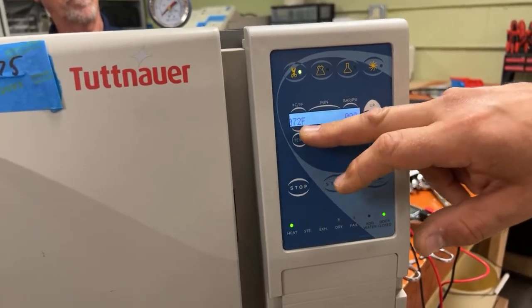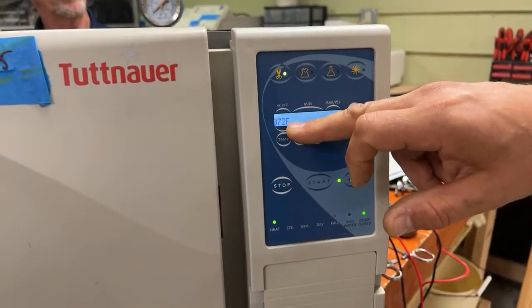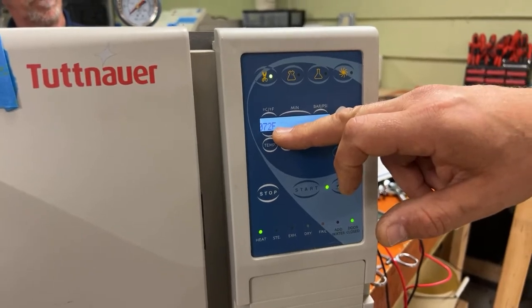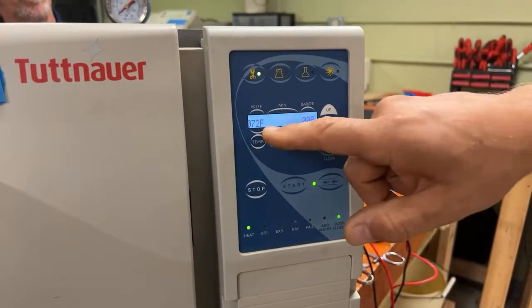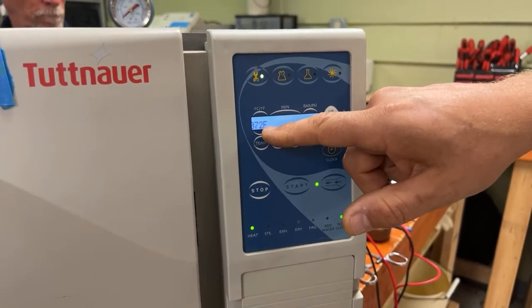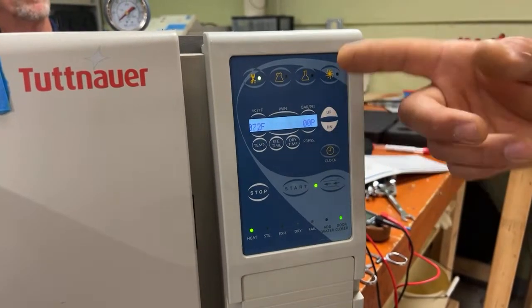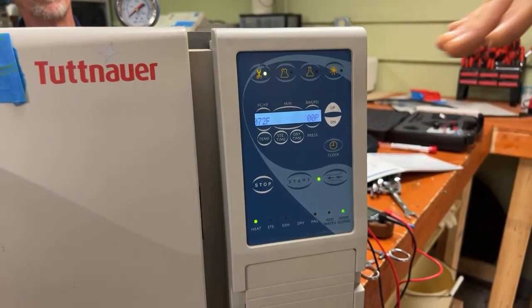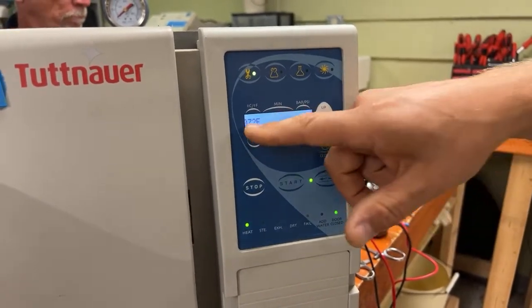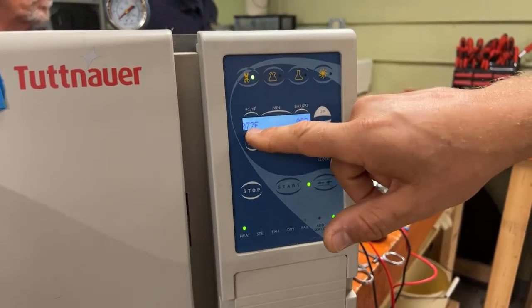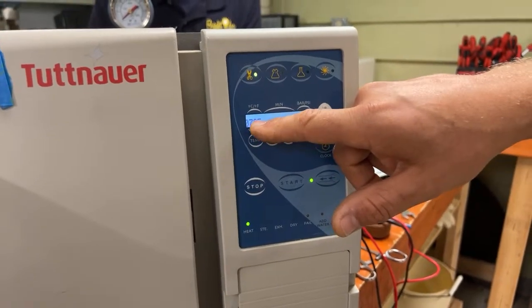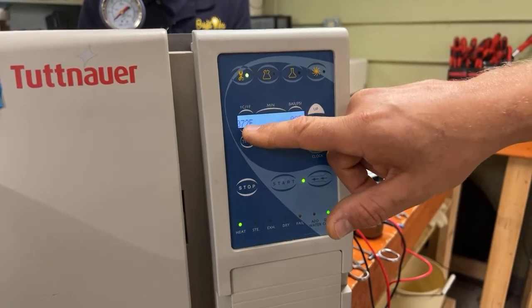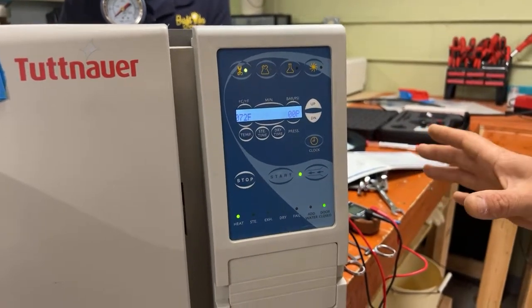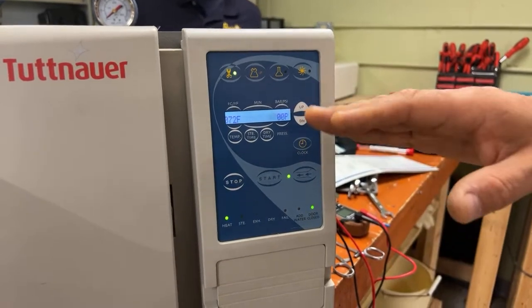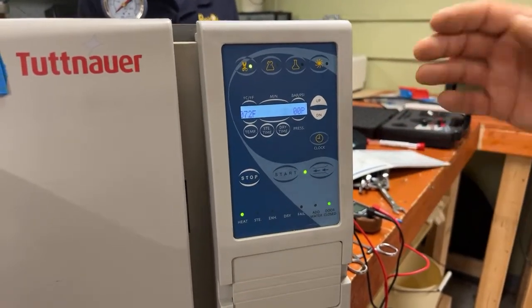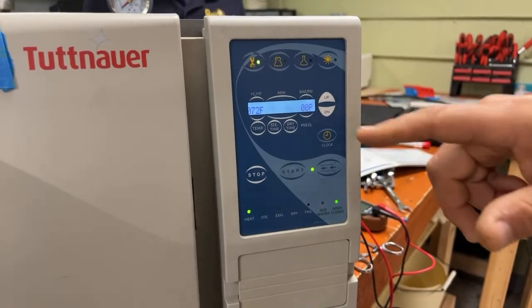So with the pressure, what we want to see is for it to be rising within probably a minute or two. We want to start seeing that number clicking up to 73, 74. And what that's going to show us is that the heating element is actually heating up in the unit. If you ever have any autoclave where it's just sitting there and the pressure or the temperature is not rising at all, then that's going to tell you that you have some sort of a problem in your heater circuit. So I'm not expecting that to be the issue here, and it will just probably take a while for that to start bumping up.